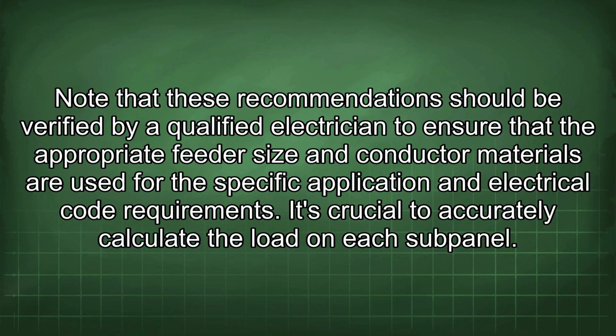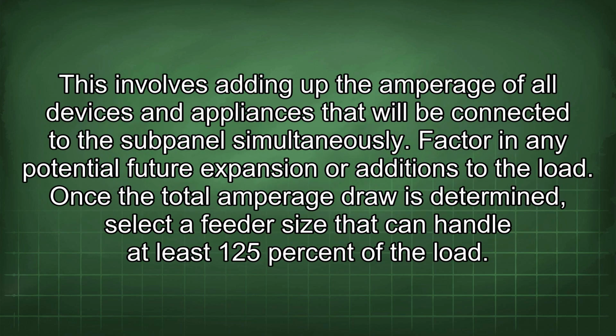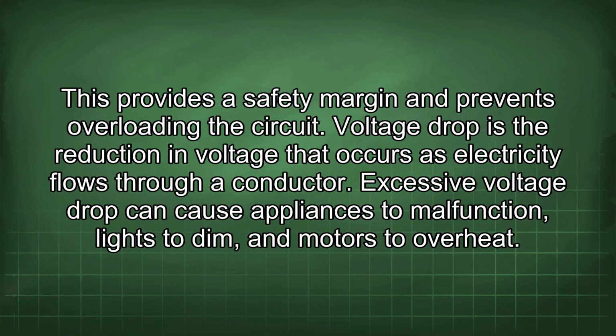It's crucial to accurately calculate the load on each subpanel. This involves adding up the amperage of all devices and appliances that will be connected to the subpanel simultaneously. Factor in any potential future expansion or additions to the load. Once the total amperage draw is determined, select a feeder size that can handle at least 125% of the load. This provides a safety margin and prevents overloading the circuit.